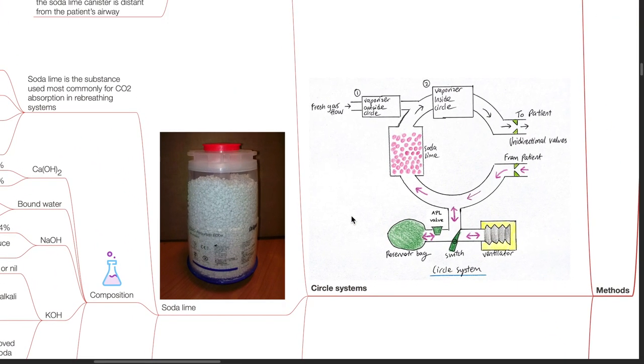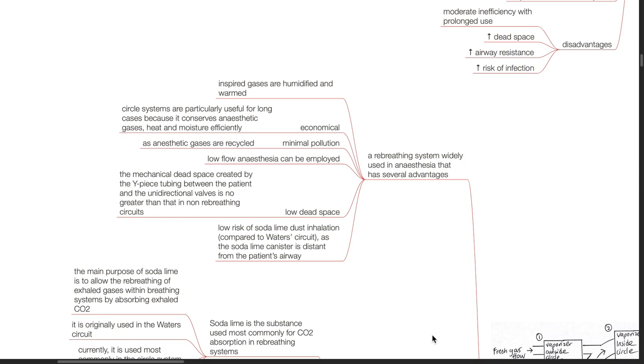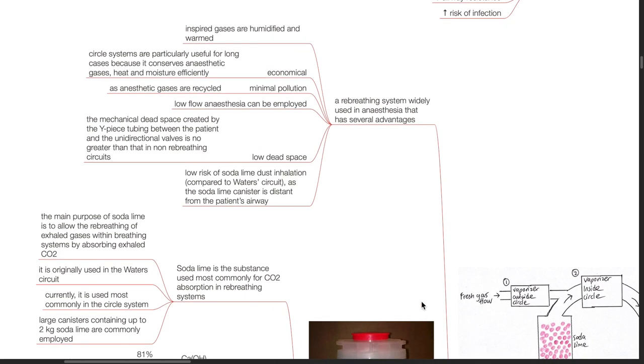Circle systems: a circle system is a re-breathing system widely used in anesthesia that has several advantages. Inspired gases are warmed and humidified. It is economical. Circle systems are particularly useful for long cases because they conserve anesthetic gases, heat, and moisture. There is minimal pollution as anesthetic gases are recycled, and low-flow anesthesia can be employed. There is low dead space — the mechanical dead space created by the Y-piece tubing between the patient and the unidirectional valves is no greater than that in non-re-breathing circuits.